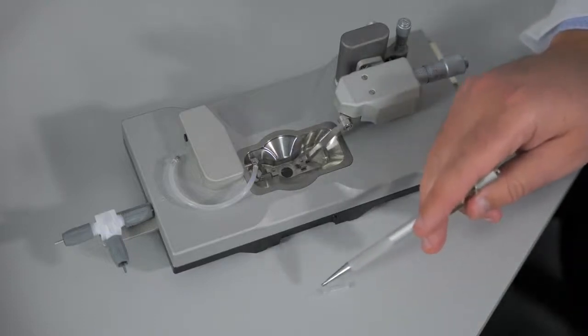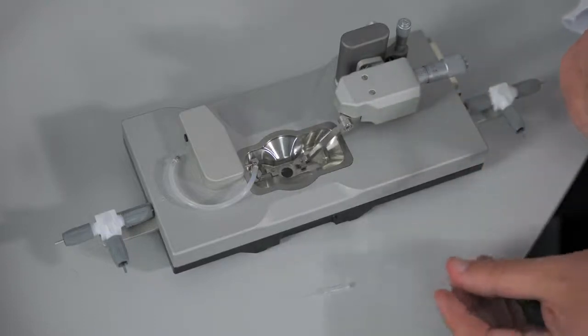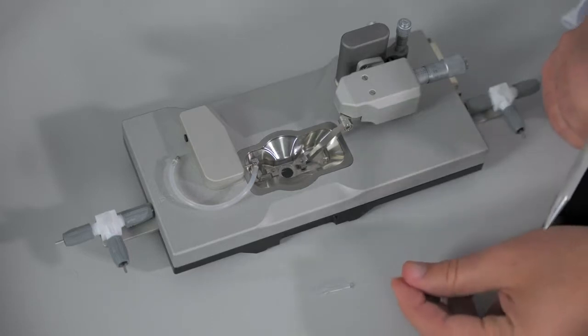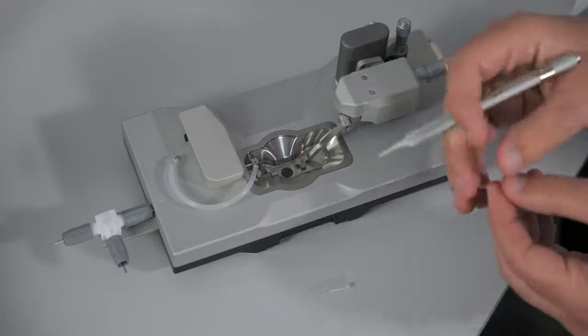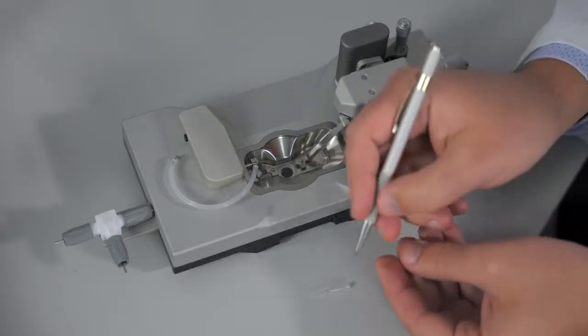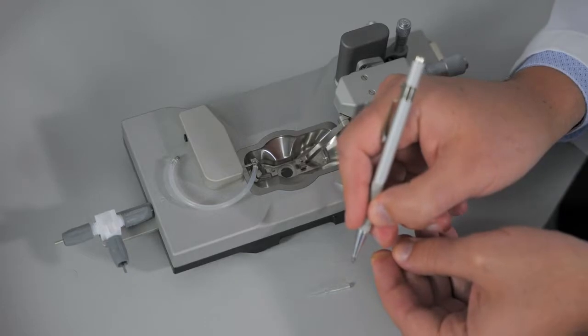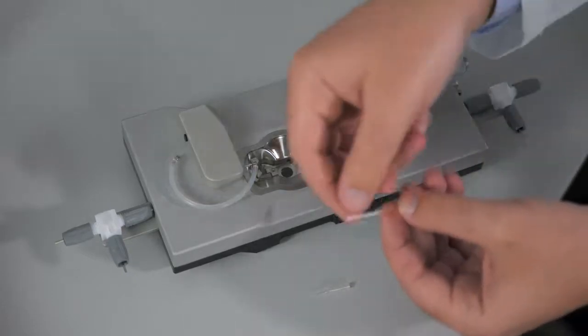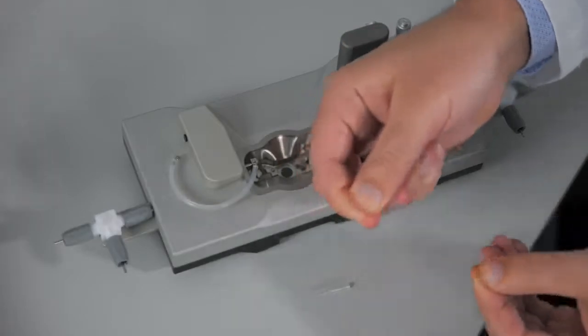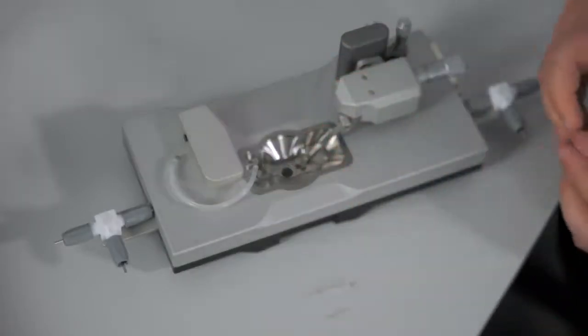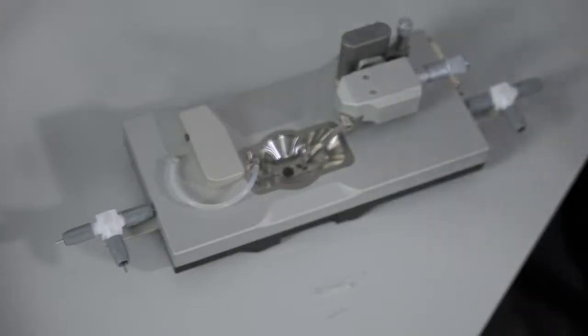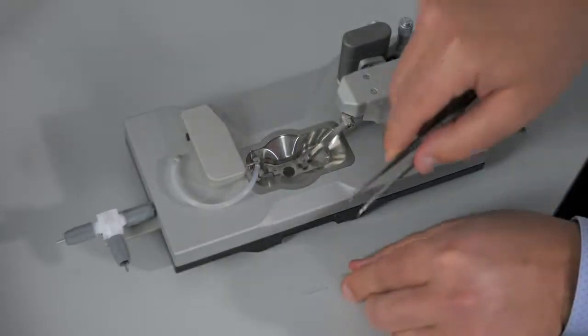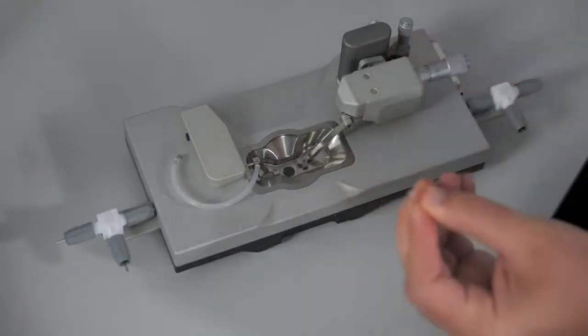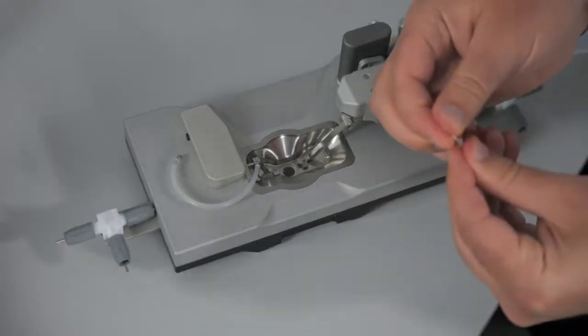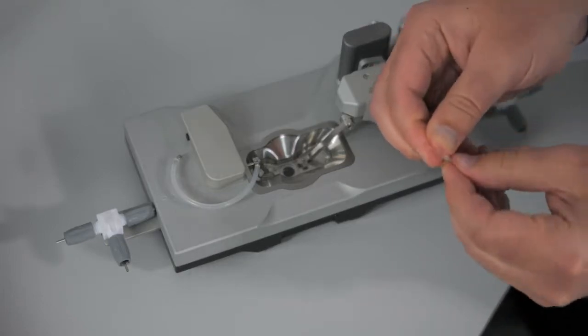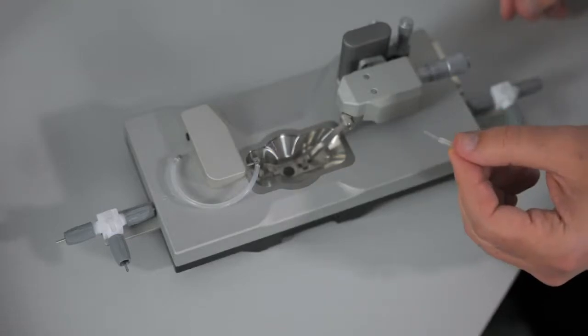You will then remove the cannula from your tubing and take one of your new cannulas and match the length to the length of the cannula that was in there before. Use a diamond cutting pen or a glass cutter to score the cannula and then break it to match the length of your previous cannula. Now you will place your new cannula into the tubing. And you will put this back into your chamber.